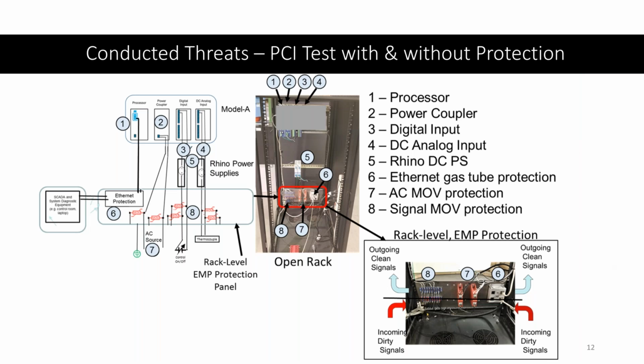With the PCI test, we also wanted to test a protected versus an unprotected mode. And so you see, this is a different view of that rack in the center. The object under test is in the top middle with the circle and arrows pointed to it. That would be the relay or the DCS components. And then at the bottom, there is a rack that was built by SARA, and there's a blow-up of that in the lower right that shows some small input-level metal oxide varistor devices. Those are for the input ports. The one labeled number 7 is at the AC power level, and number 6 is a spark gap to protect the Ethernet port.